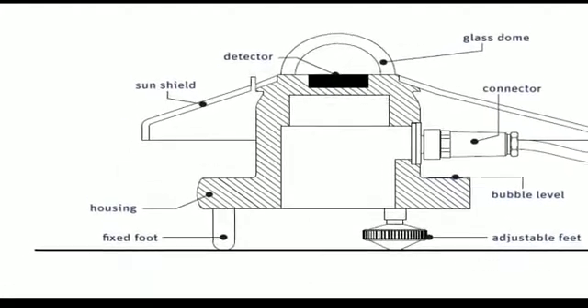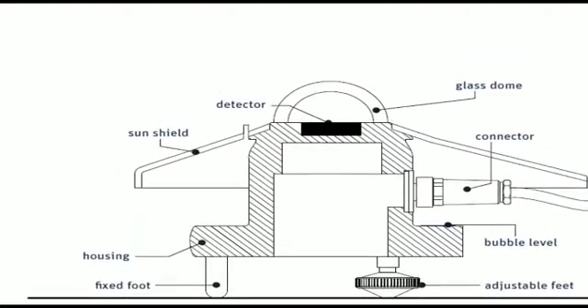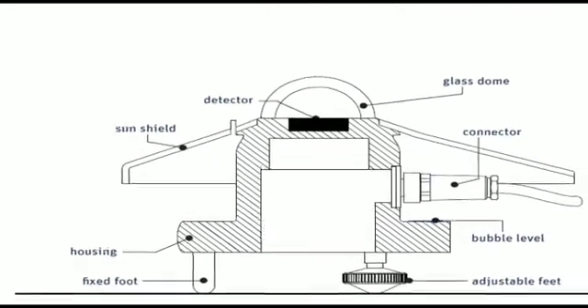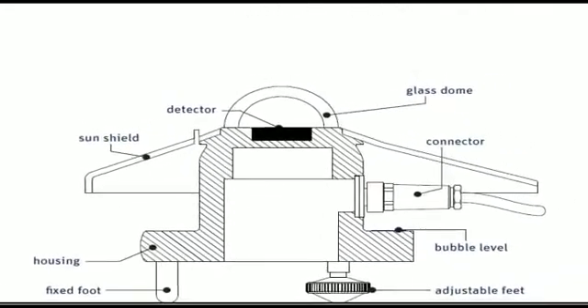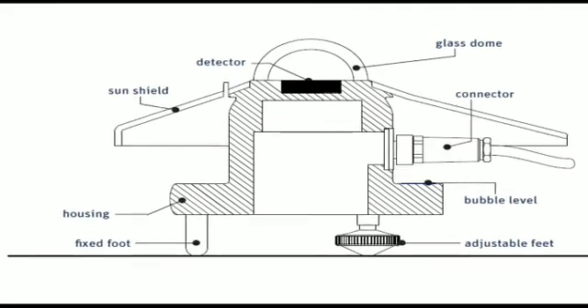This is the construction of the pyranometer. We can see its parts: a sun shield, a detector, a glass dome, a connector, a bubble level, a fixed foot, and housing. When placed in the sun's rays, it receives radiation, causing the temperature of the absorbing surface to rise. This rise in temperature is detected by a thermopile, which generates a thermo-EMF proportional to the radiation absorbed. This thermo-EMF is calibrated in terms of received radiation.